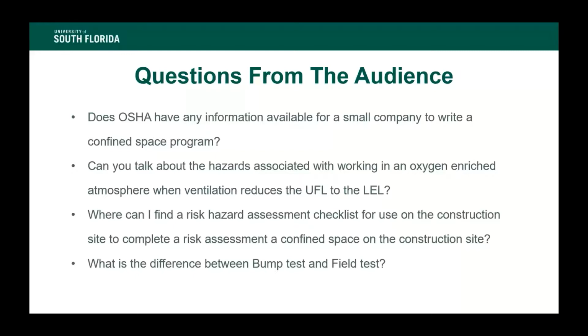Our next question. What is the difference between bump test and field test? Bump test is when you use the calibration gas to create a reaction on your running monitor to see if the alarms, the audible and the visual alarms, are properly working. Therefore, the sensors are actually in good condition. Field test, it's a more generic term.